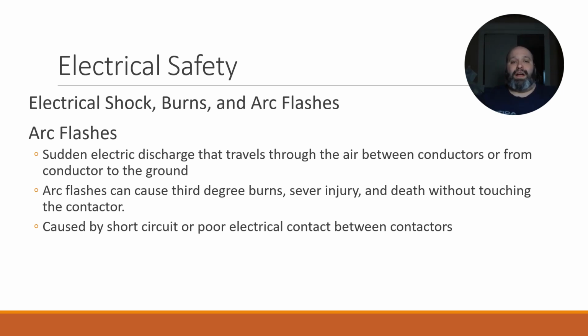So, what is an arc flash? An arc flash is a sudden electric discharge that travels through the air between conductors or from the conductor to the ground. Arc flashes can cause third-degree burns, severe injury, and death without even touching you. A lot of us think of an electrical shock or electrical burn as happening when we've contacted a bare wire, or power is somehow traveling through the case of a machine. Maybe an insulator has rubbed off, and so we get shocked by touching the cabinet of a furnace. But you don't even have to touch a part of the circuit.